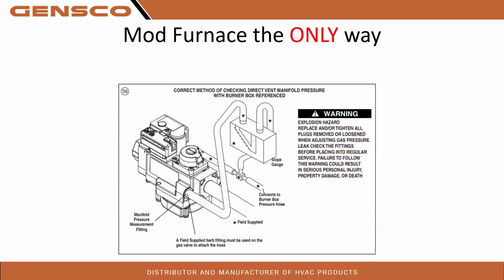valve maximum setup, because it can give you a PS1 failure. When you do the gas valve minimum maximum setup, it actually sizes the flue pipe that you ran to the inducer motor speeds, and it correlates those. So if you never do gas valve setups, min and max, and you never do this at all after an install, you're going to have some problem. It may work for a while, it's going to complain, but eventually you're going to get a call on it. So make sure you do this.